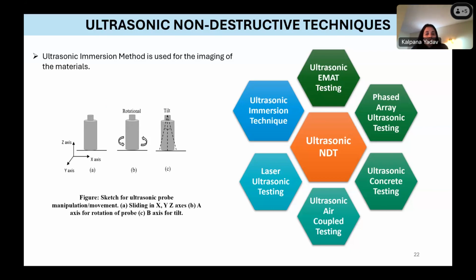If you have a complex specimen with irregularities, you cannot use the ultrasonic contact method, so you need an alternative. In that case, you can use ultrasonic EMAT testing, where you don't need to make direct contact. And phased array testing is, I'll say, a more upgraded version of ultrasonic testing. Here we are using only a single transducer with one disk that generates a single pulse and receives the same pulse. But in phased array testing, there are multiple transmitter signals and multiple receiver signals, so you have a lot of signals that can be analyzed based on the time delay, the time difference while you are receiving them. So it depends on the application which testing you are going to use. Mostly I'm talking here about ultrasonic immersion testing and the ultrasonic contact method.